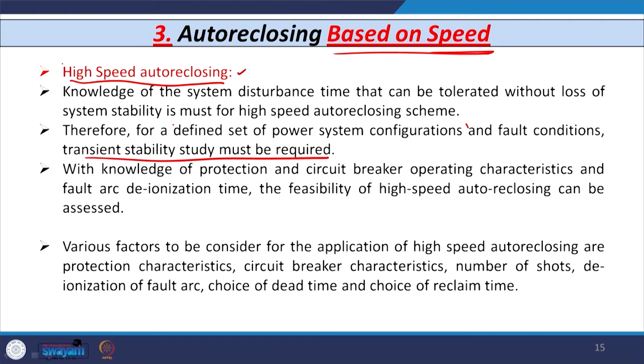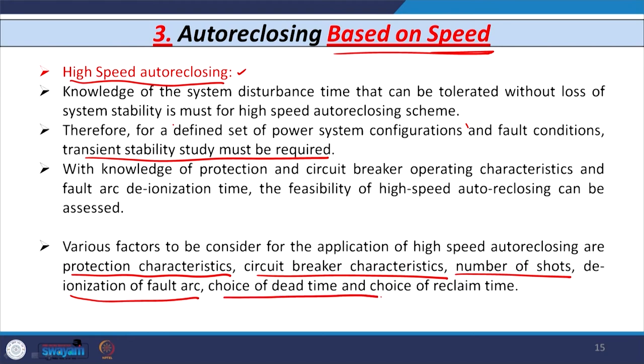Factors to consider for high-speed auto reclosing include: protection characteristics, circuit breaker characteristics, the number of shots (single or multiple reclosing attempts), deionization time of the fault arc, and the choice of dead time and reclaim time.